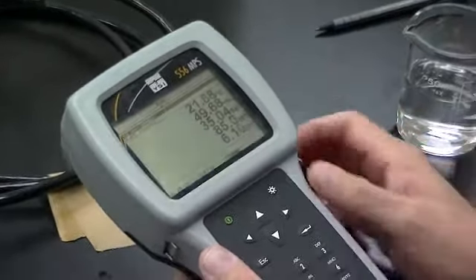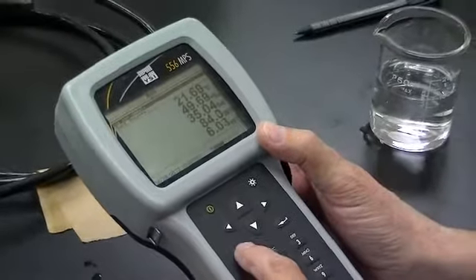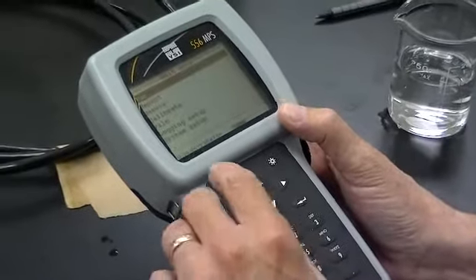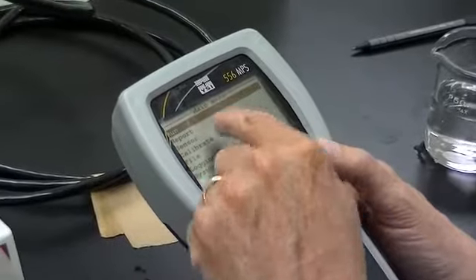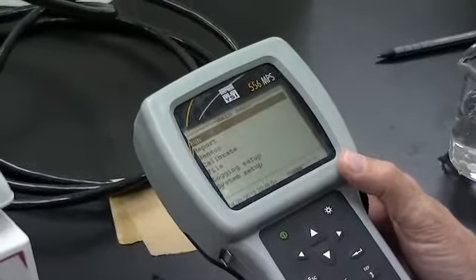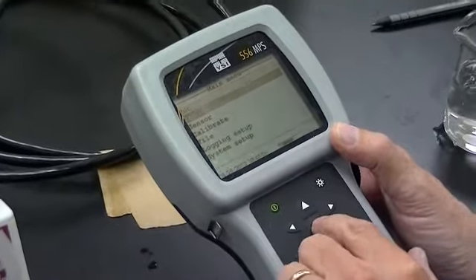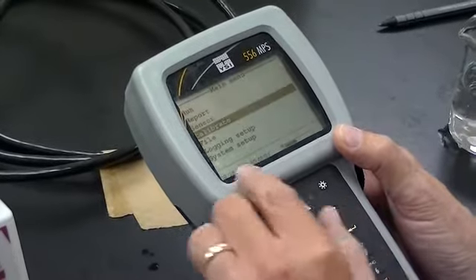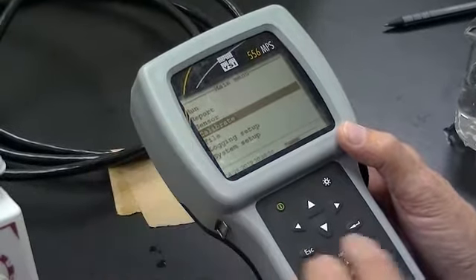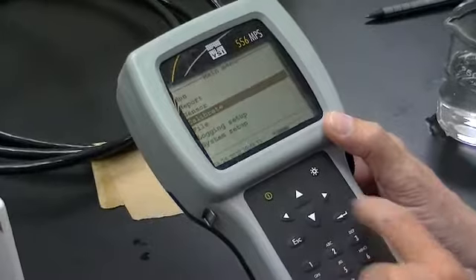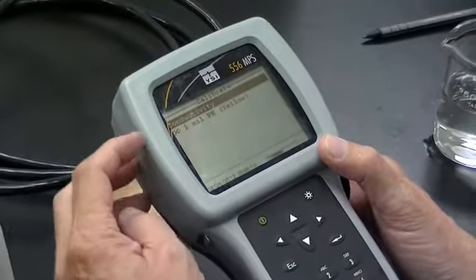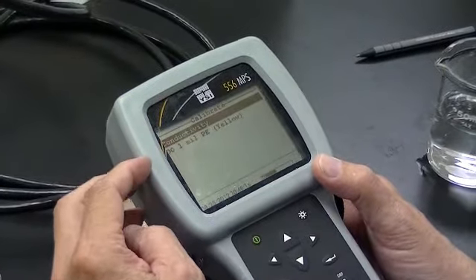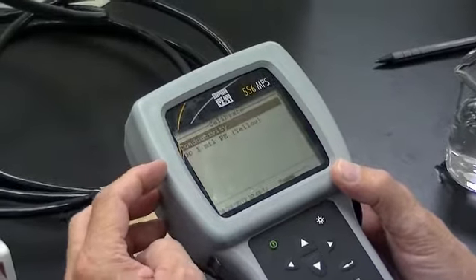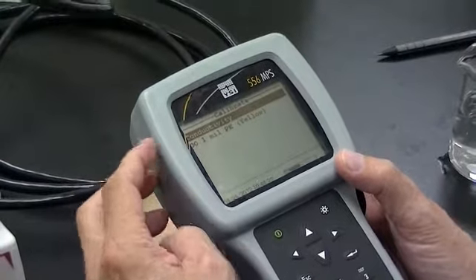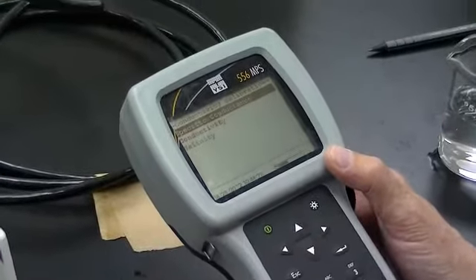Okay, now to calibrate it, you push the escape key to go to the main menu. See, it says main menu right there. Can you see this? Okay, and you use the down arrow key, 1, 2, 3 clicks, until it indicates calibrate, and then you hit return just like a computer. And now you have two choices, conductivity and DO. That means dissolved oxygen.